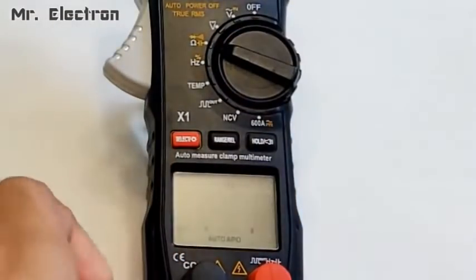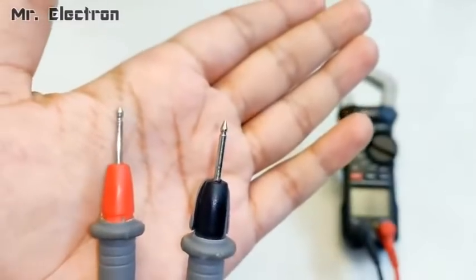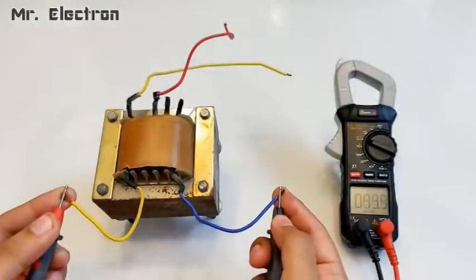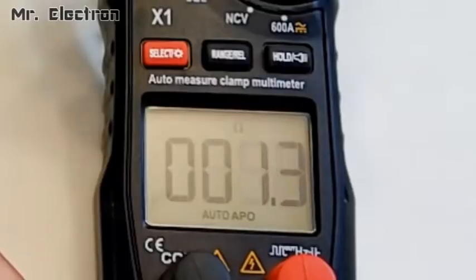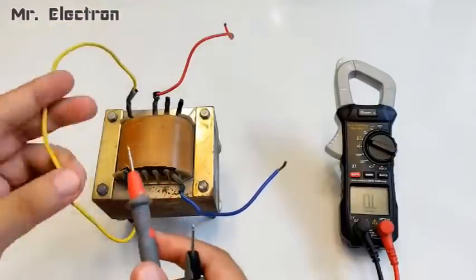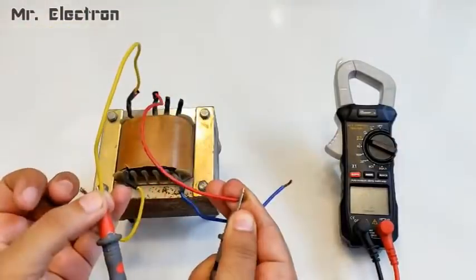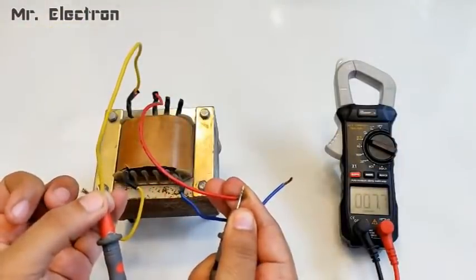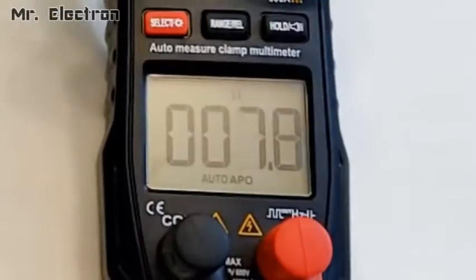Here I'm doing a resistance check. As you can see, this side shows only 1.3 ohms, so it's the low voltage secondary side. The other side shows 7.7 ohms, so that side becomes the high voltage side.